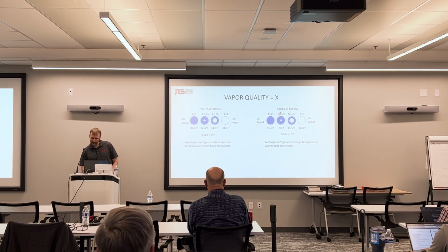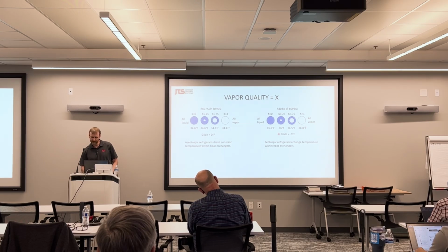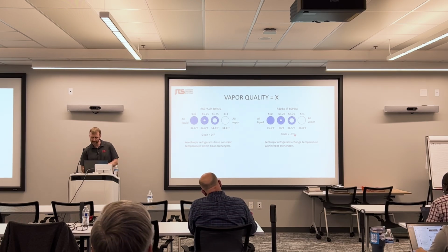Azeotropic refrigerants have constant temperature within the heat exchanger. R404A and your zeotropic refrigerants, for instance, change temperature as that liquid boils. So R404A at 80 psi with 100% liquid is going to have a temperature of 35.9. If you've got 100% saturated vapor, your temperature would be 36.8. The difference in these temperatures is your glide, which in this case is 0.9 degrees.